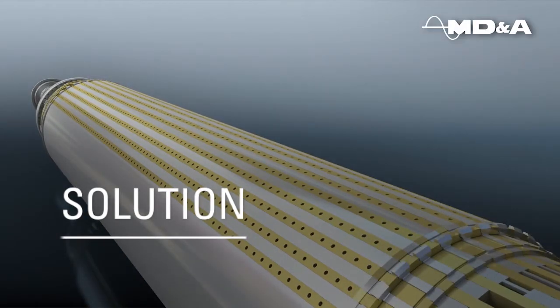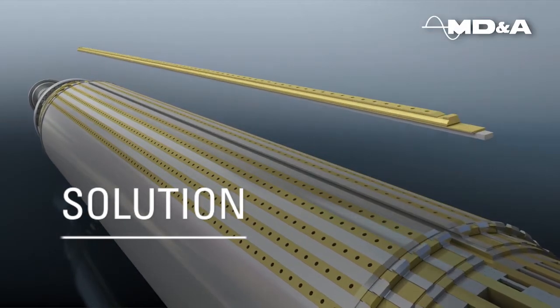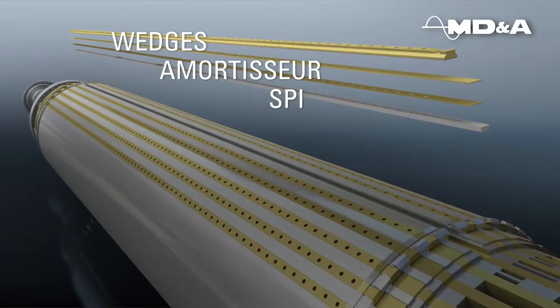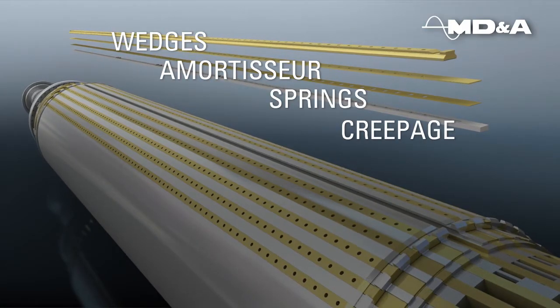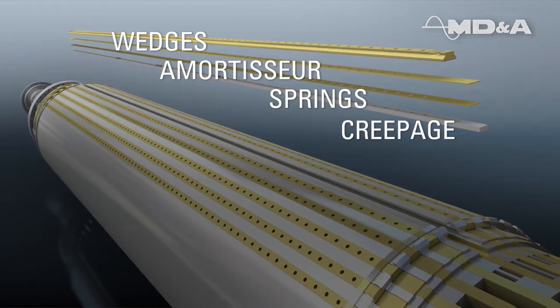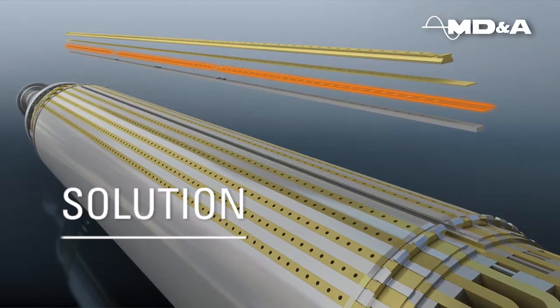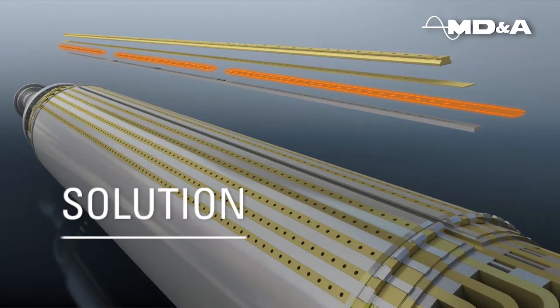This new design created by MD&A's experts has fewer springs and a top hat piece that secures the springs in place with the wedges and an amortisseur over the creepage assembly. The original design had several springs all down through the slot. MD&A's new design reduces the number of springs to just three to hold in location.